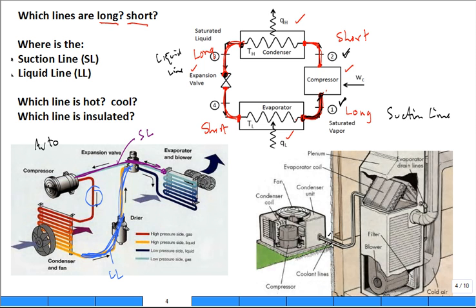So which line is hot? Is it the suction line? Is that the one that's hot? Or is it the liquid line hot? The liquid line? We have a vote that the liquid line is hot. People agree? And the suction line is cool. And in the automotive application, you could probably put your hand on this one. That would be a discharge line. Discharging from the compressor, going toward the condensing coil, condenser, and that'll be really hot. You touch that, you're going to burn.